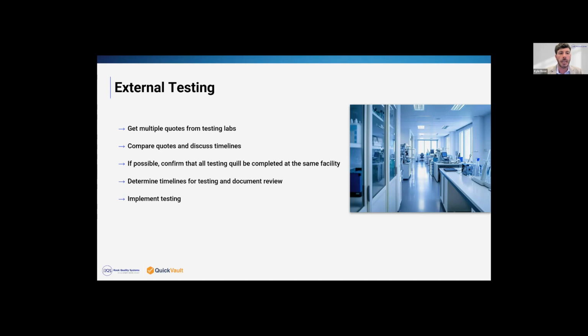Also very, very key is to determine timelines. Some of these labs can be busier than others, so make sure that your device will get tested and be a priority, aligned with your goals for your FDA submission. Once all that's been reviewed, quotes have been signed, and payments have been sent, then you can send your device for testing. It's also good, when you're interacting with the testing labs, to identify how many devices and how much material they'll need to do proper testing, so you can plan that in your manufacturing batches for testing.